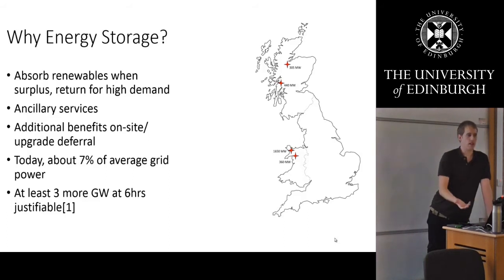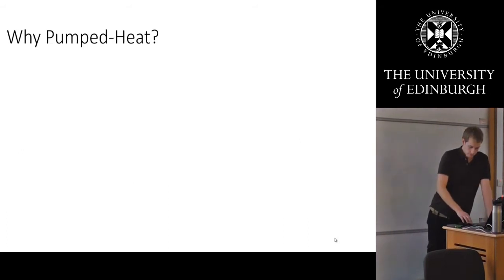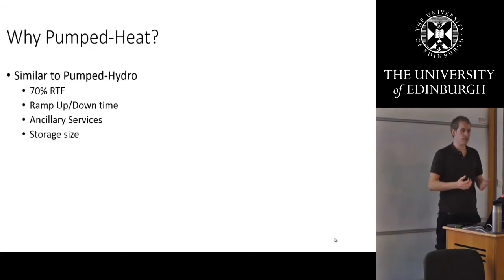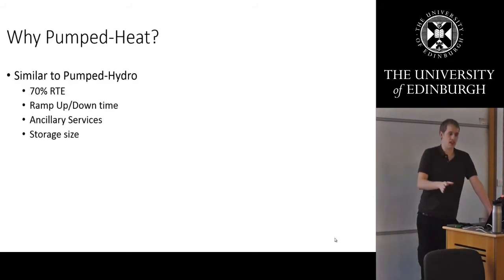So why do we think our technology is good? Well, short answer is we think we can be similar with existing standard, which is essentially pumped hydro, in good ways. And dissimilar with it in some other good ways. So what that means is roughly a 70% round-trip efficiency. That's AC efficiency, including your inverters, including your grid, all that stuff. Similar ramp up and down time, similar ability to provide ancillary services, and similar, ultimately similar storage size.